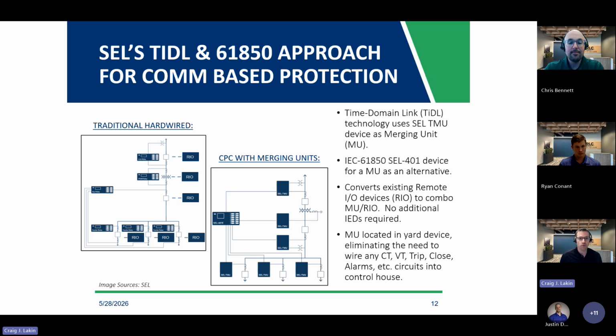And the big benefit with the communication-based approach is you're getting all the same consolidation of relays. You're going from 7, 8 relays to 1 relay. The benefit being that you have the ability to wire your CTs and VTs to merging units out in the transformer or breakers, and then having sampled values come back to your relay, eliminating control wiring and CT and VT wiring to and from your control house to your yard devices, which makes the design much more modular, easier to adapt. It also eliminates some of the hazards and concerns of CT and VT wires between the control house and the yard devices.